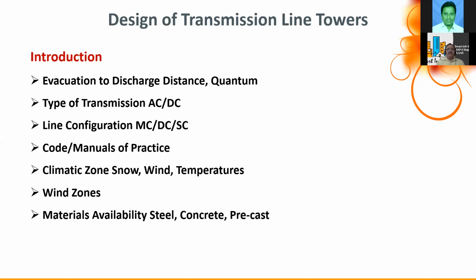So we all know the conductor sag also, because it's a flexible cable actually. So the conductor sag is important. Again, sag is dependent on the temperature. Higher the temperature, more is the sag in the cable. And in India, we have wind zones ranging from 33 meters per second to 55 meters per second. That means 120 kilometers per hour to 200 kilometers per hour. And we have wind speeds exceeding even 200 kilometers per hour.